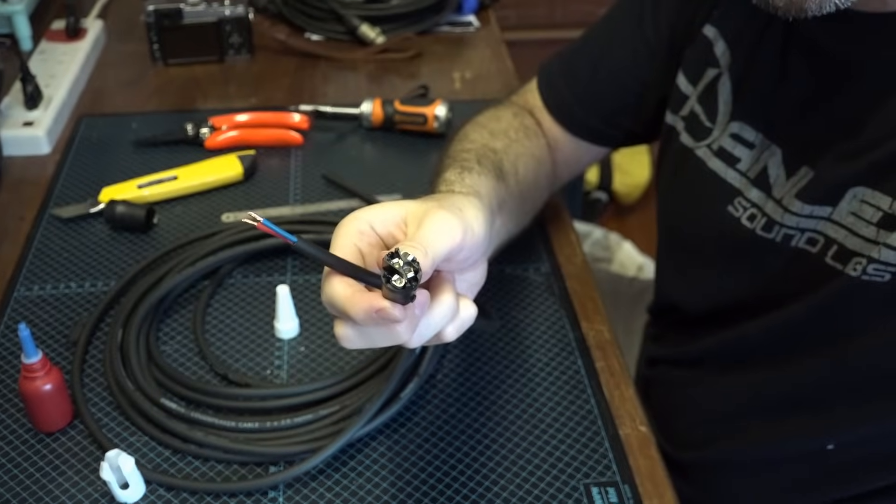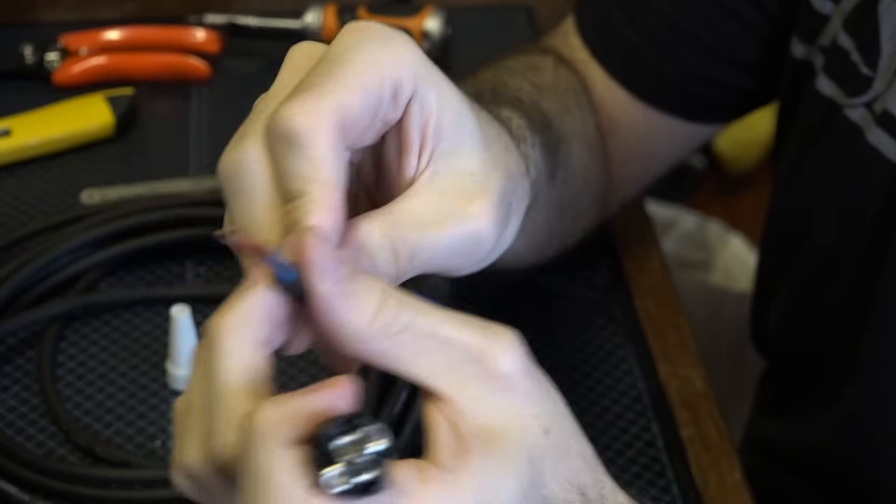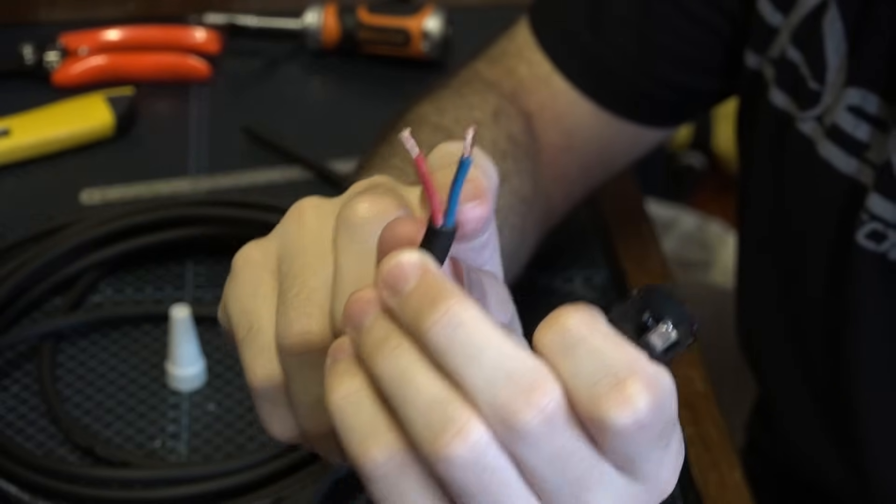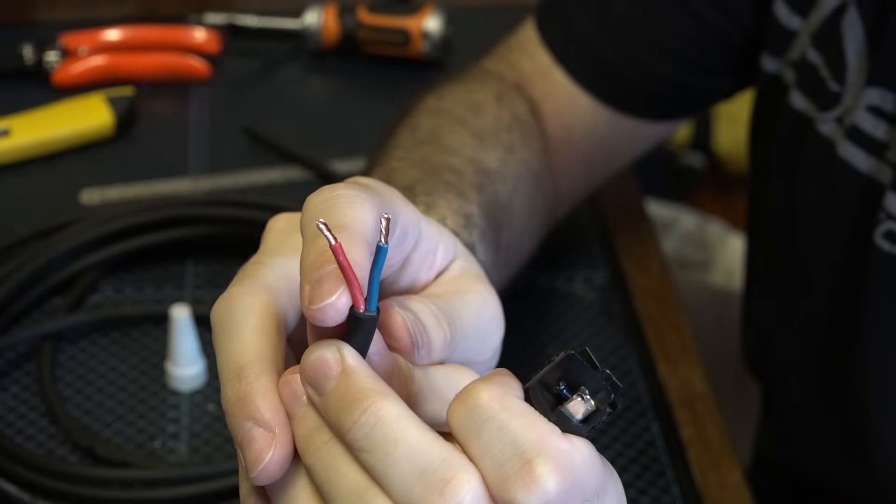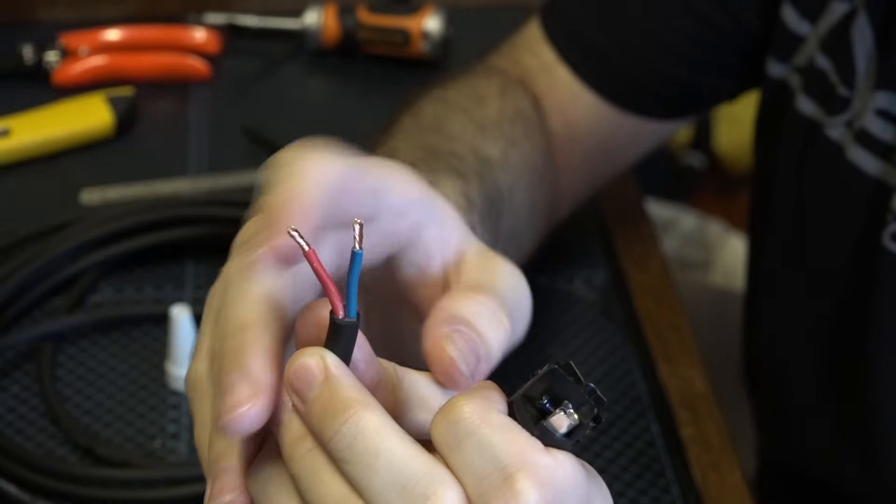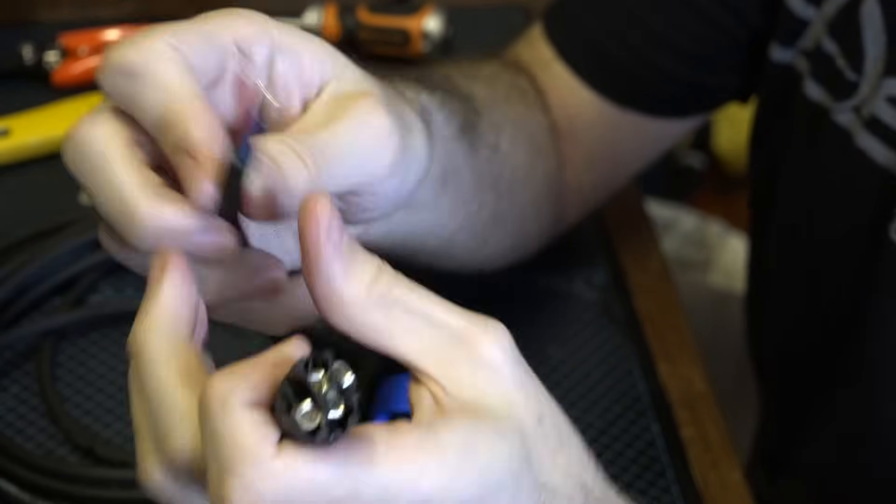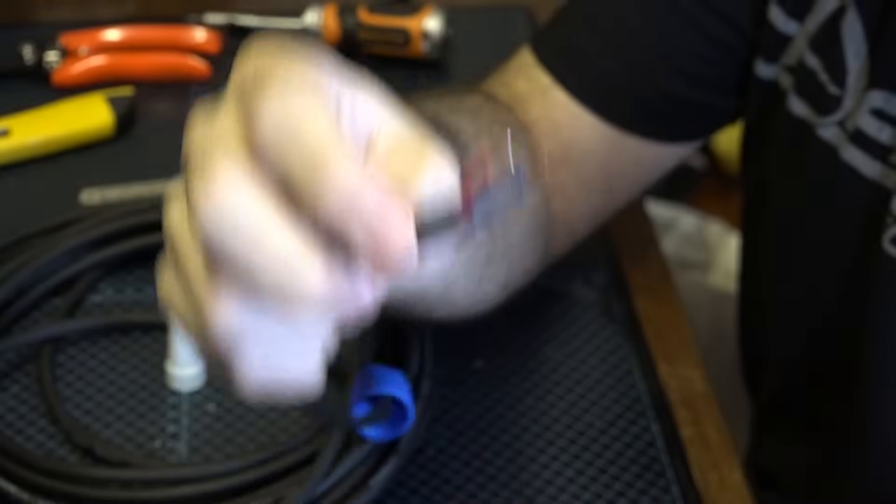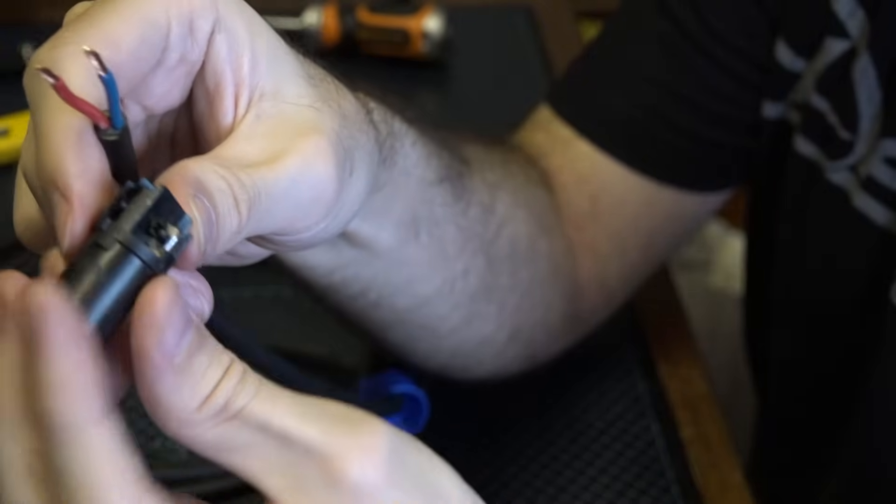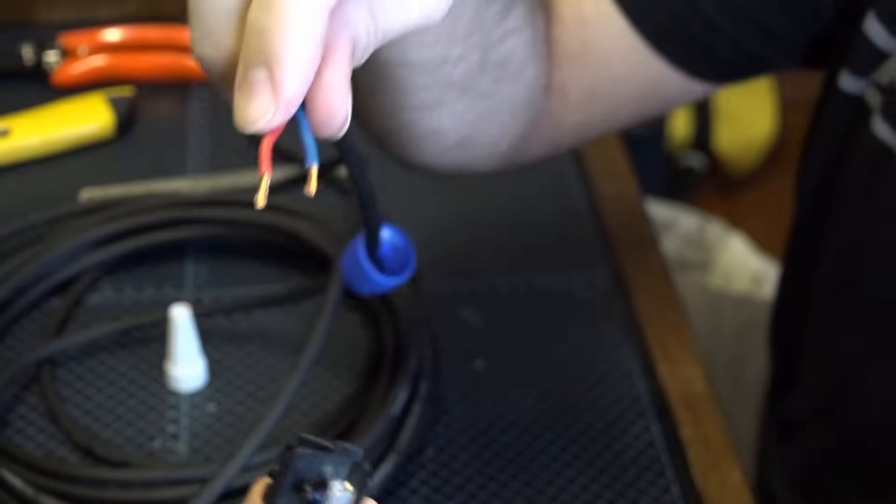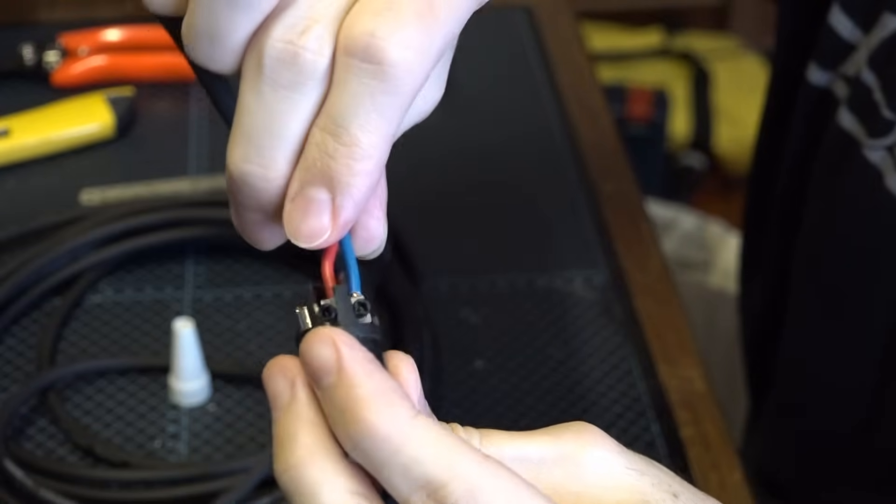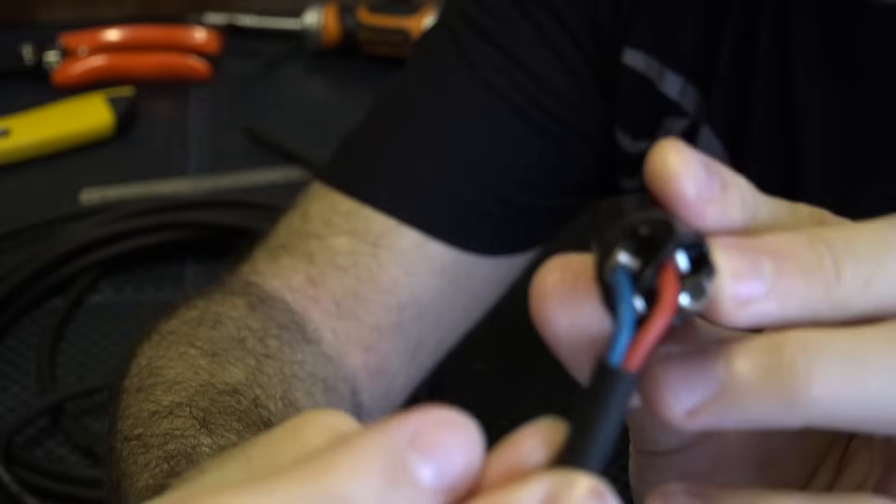I'm gonna bring you in a little bit closer here so that you can see what's going on. All right, so now you can see that you've got a red and a blue conductor. Sometimes you'll have a red and a white. Convention is that red is always plus one or plus two, in this case it's plus one, and blue is always minus. So red hot and blue cold. I like to bend these so that they are approximately the same distance apart as the distance between the terminals there. Then what I'll do is I just feed them straight in. This bit is a little bit hard to see, so I'll try and do it there. So I just feed them in.